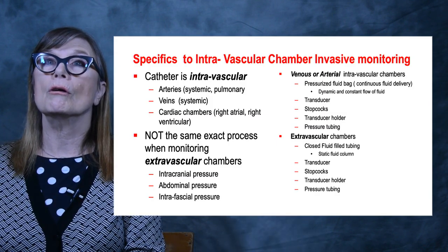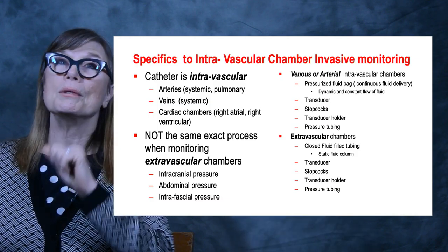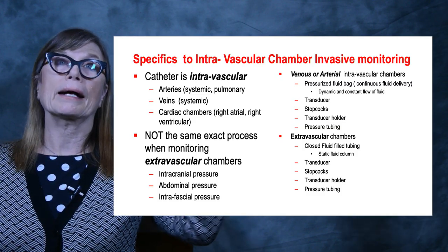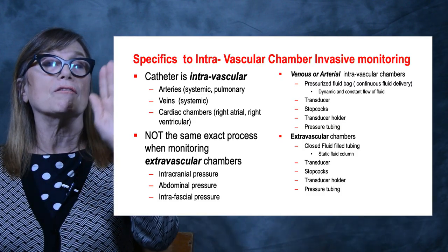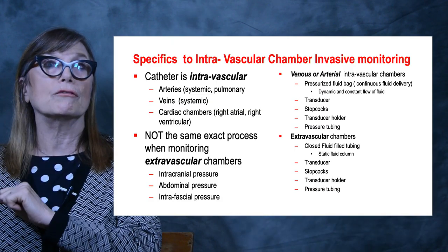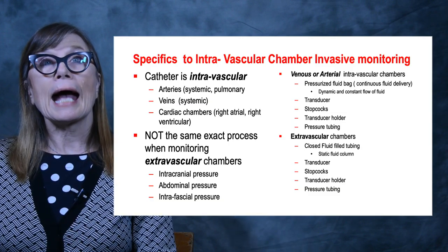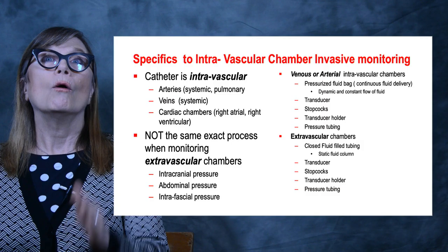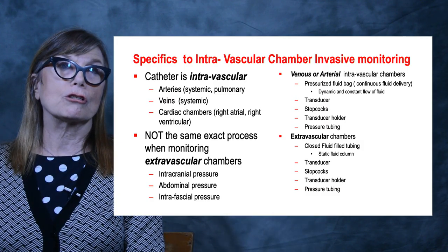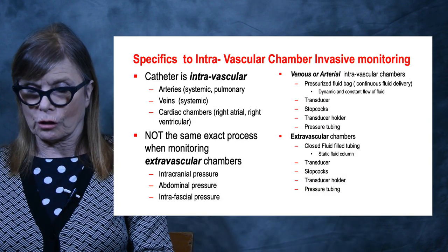A transducer, stopcocks, transducer holder, and of course, that closed fluid system, which is the pressure tubing, but no pressurized bag. So very important to appreciate the difference between intravascular pressure monitoring, requiring a pressurized fluid bag for a dynamic column of fluid, and extravascular chamber monitoring, which actually does not allow you to have a pressurized fluid system, always pushing fluid through a transducer.